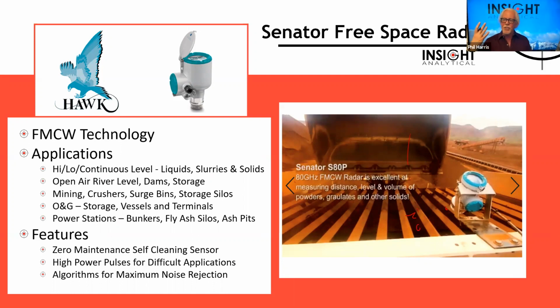The problem with a lot of level sensors is if there's a device in between them, they pick up a reflection or they sense the level of that device. In this case, a lot of level sensors would measure how far it is to these bars. That's not what we want to know. We want to know how far below the level of those bars is the material I'm filling that tank or that bin with. And the nice thing with the Senator Free Space radars is they have a very narrow beam. We can align them such that we can make those measurements between these sorts of devices or around interfering devices. And in doing that, get a very reliable, accurate measurement of level in difficult type applications.